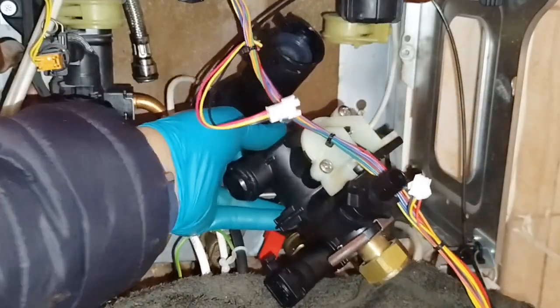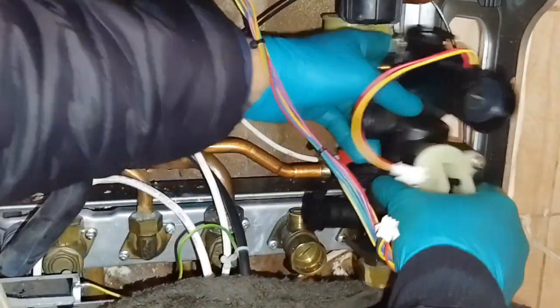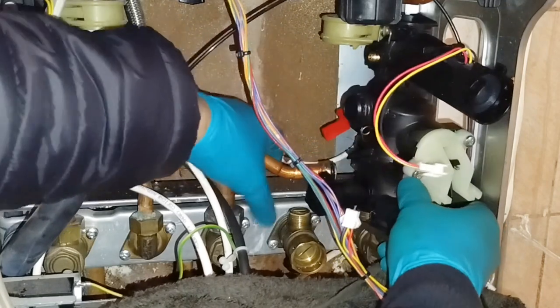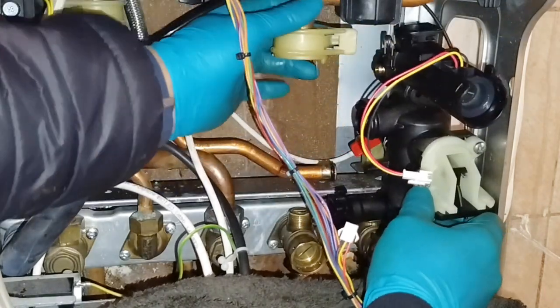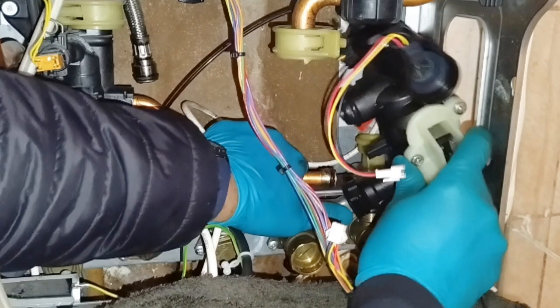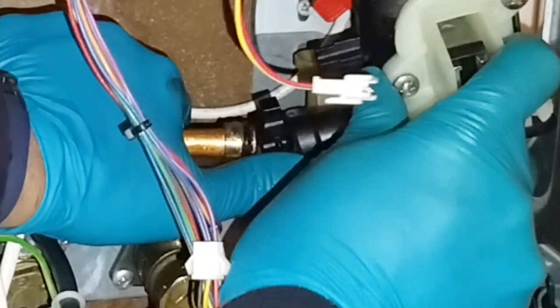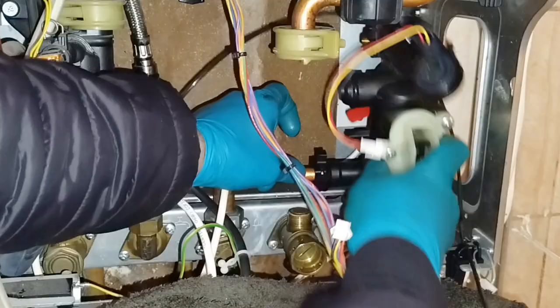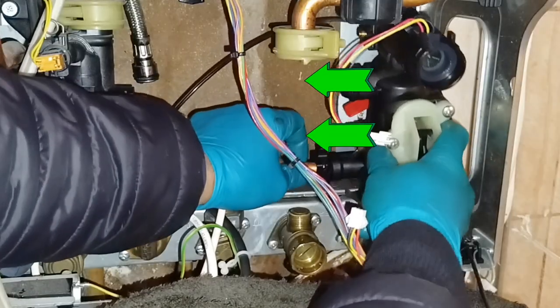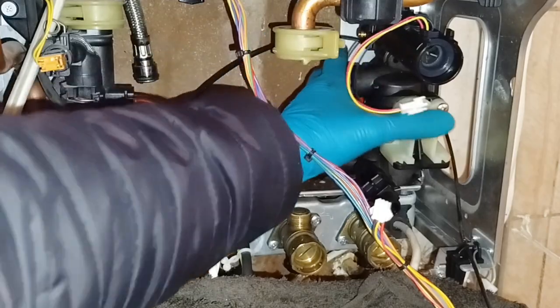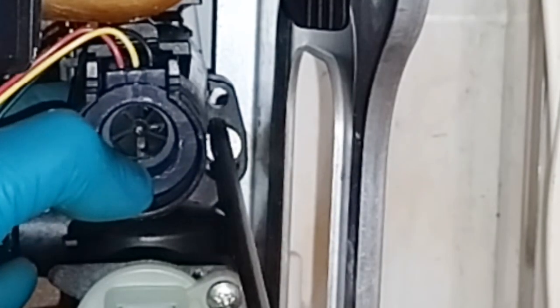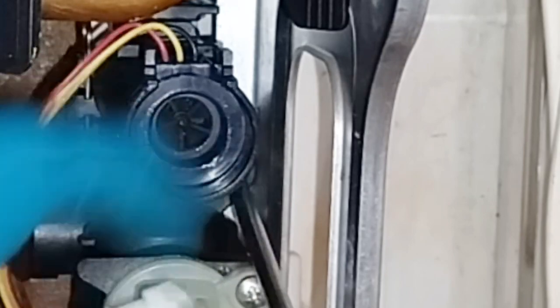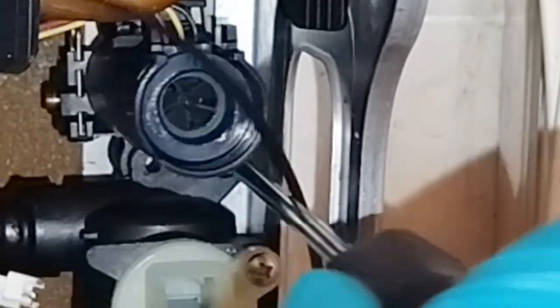All right, after this we will slide the return assembly in, but we will put it in sort of diagonally and pushing the front towards the left side, so we can put the whole assembly in. See, we've tilted it slightly diagonal, so we can put the bypass in easily. If it's lubricated well, if the O-ring is clean, it will go in nicely. Okay, make sure you push it leftwards so the manifold has gone onto the bypass. Okay, so to keep the bypass in place, we will loosely put the screw into the boiler's chassis, the boiler's body, so the manifold is held in place.